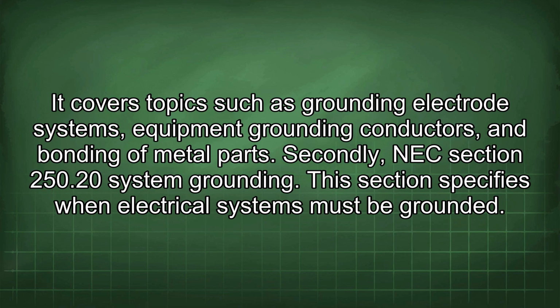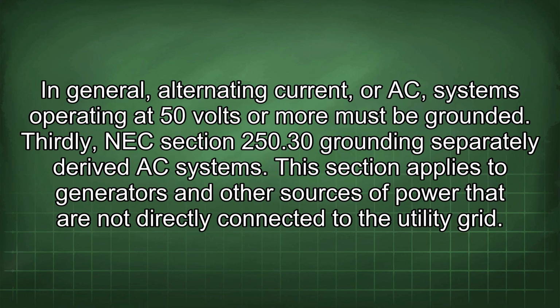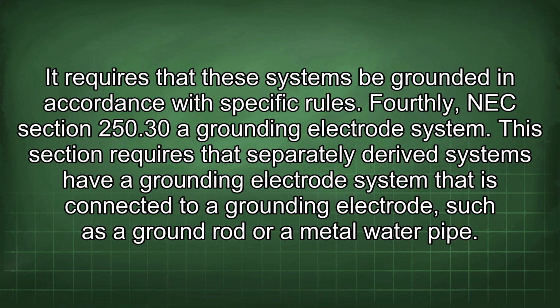Secondly, NEC Section 250.20 System Grounding. This section specifies when electrical systems must be grounded. In general, alternating current, or AC, systems operating at 50 volts or more must be grounded. Thirdly, NEC Section 250.30 Grounding separately derived AC systems. This section applies to generators and other sources of power that are not directly connected to the utility grid. It requires that these systems be grounded in accordance with specific rules.